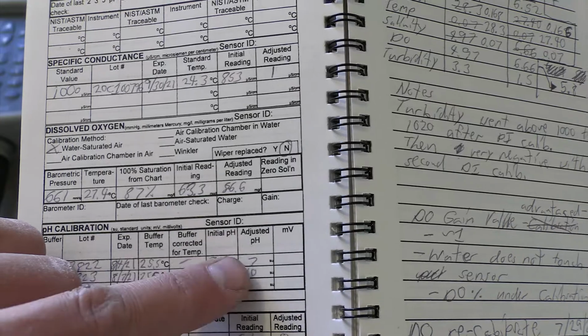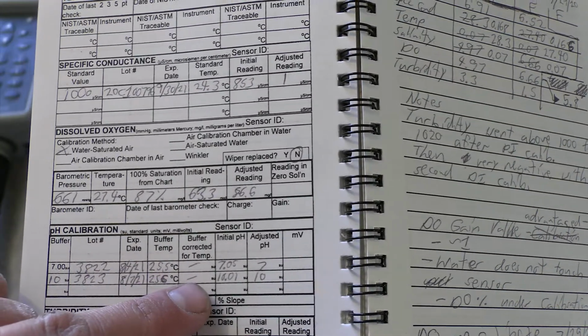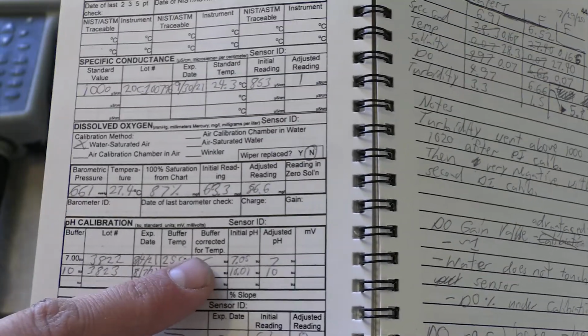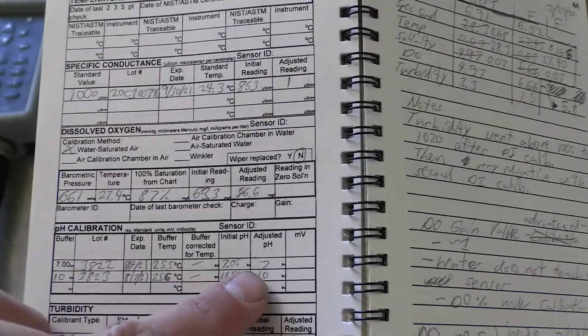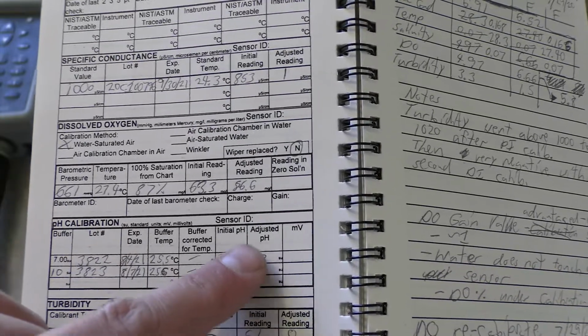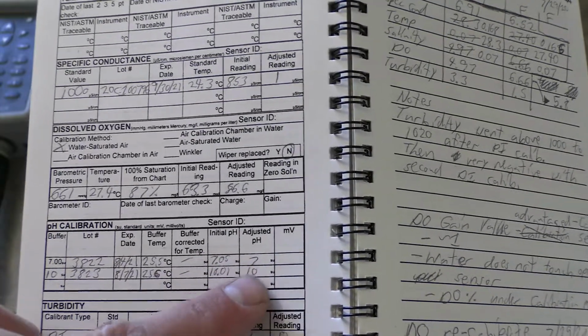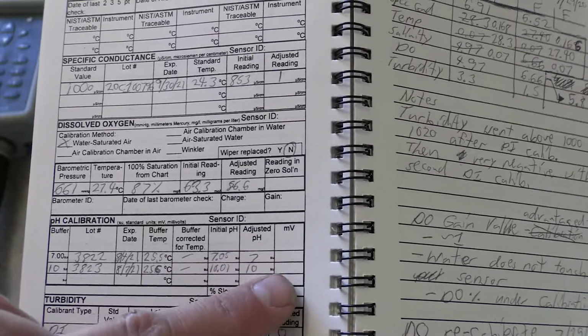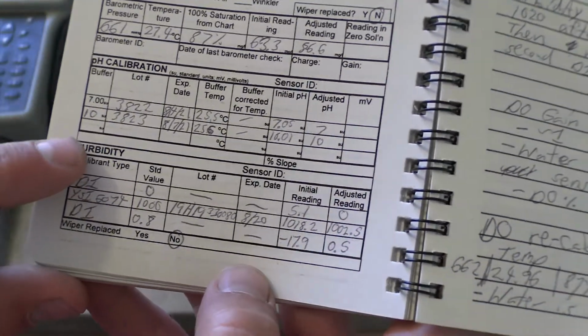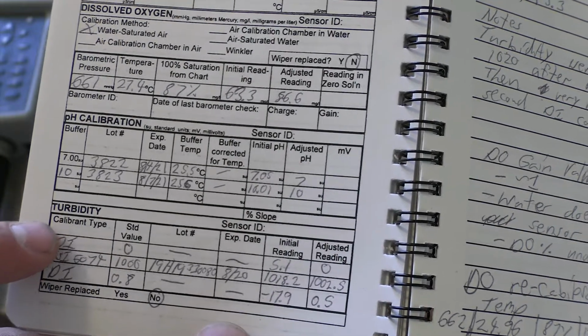Okay? And then the final pH, which should be the same. So the adjusted might actually be 7.04 or 10.07, something just slightly different. In that case, the adjusted pH would actually be 7.04 or 10.07. And then we can put in our millivolts, but it's not super important. The two should align correctly. And then, okay, so then we go down to turbidity here. And turbidity is the last sensor.